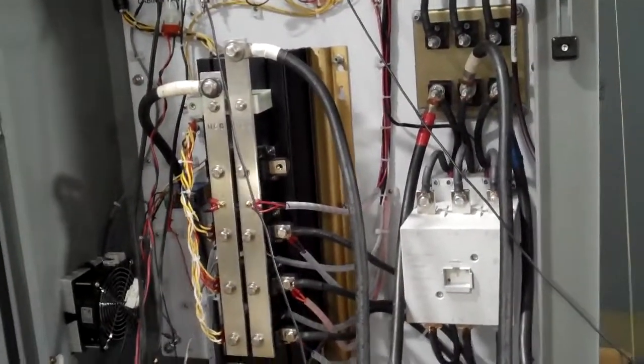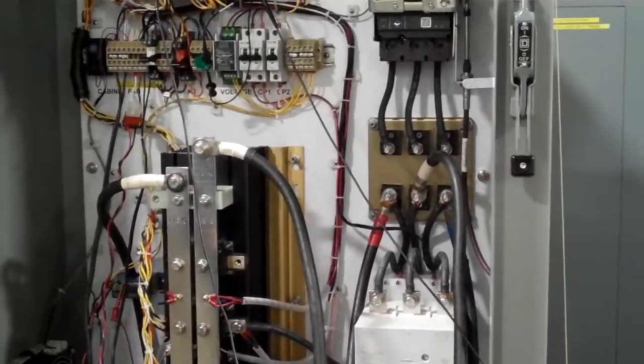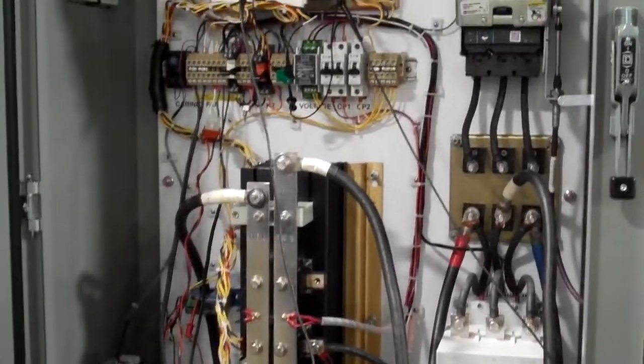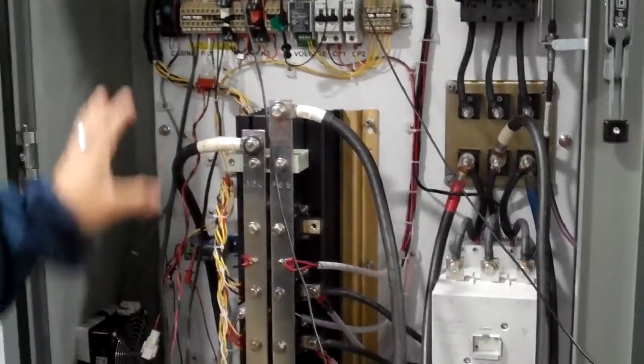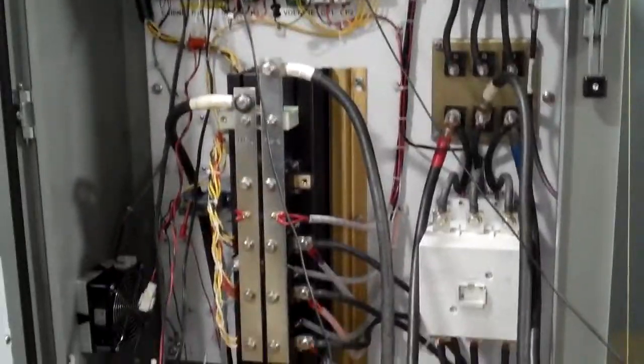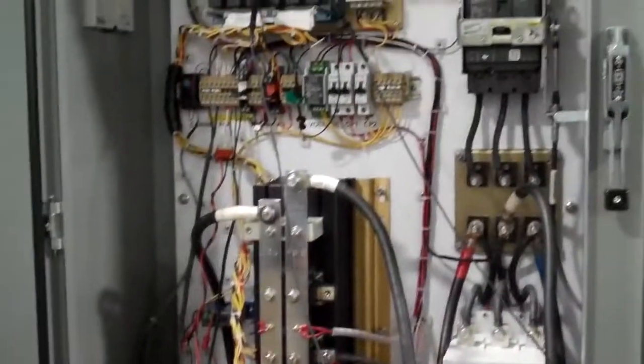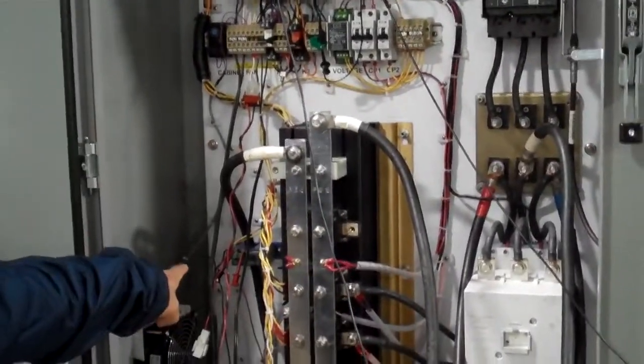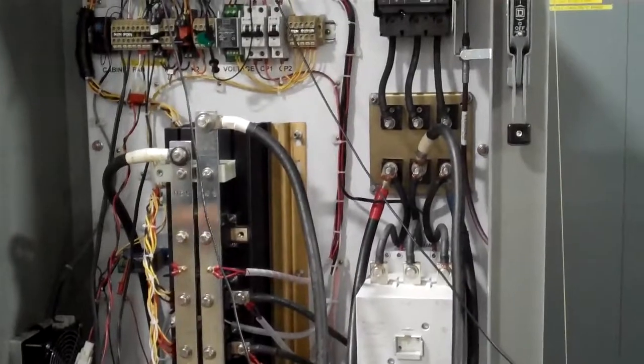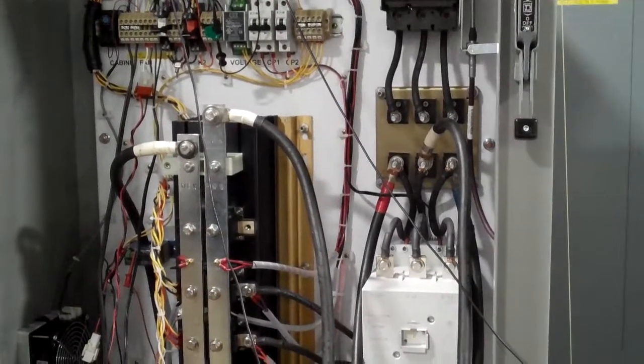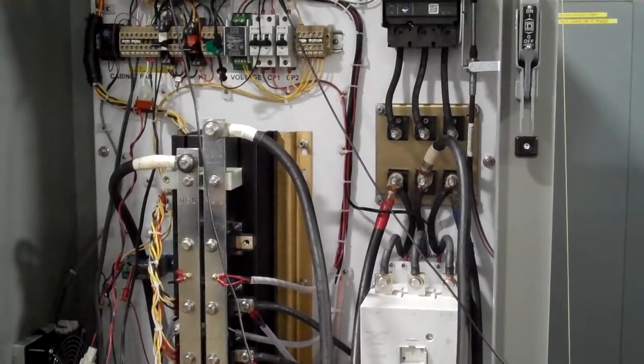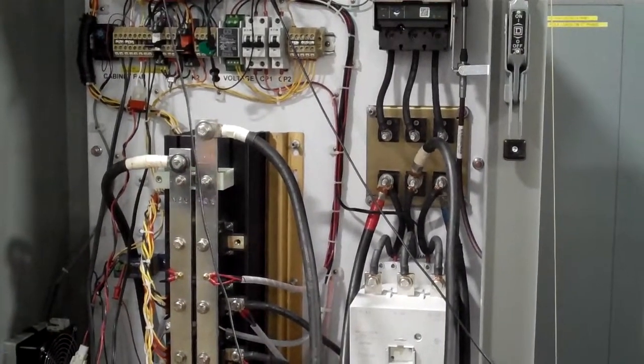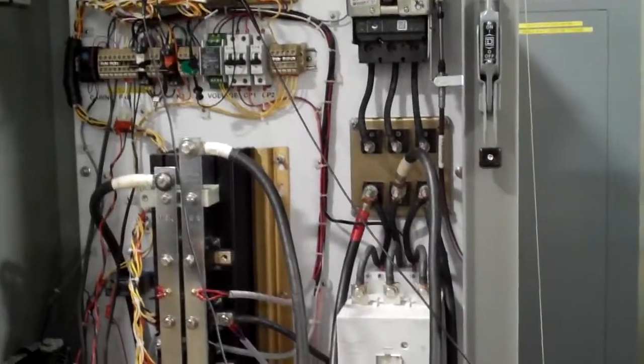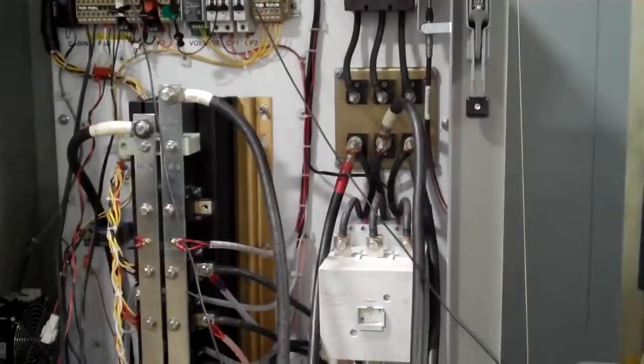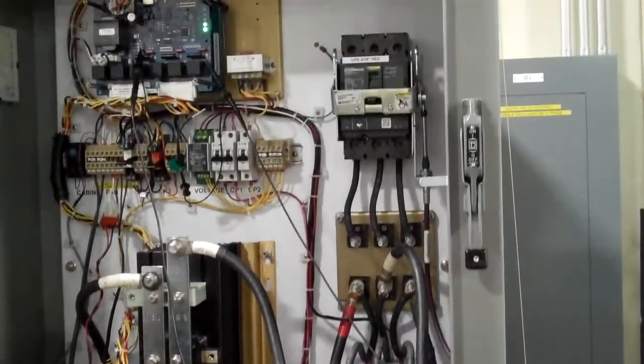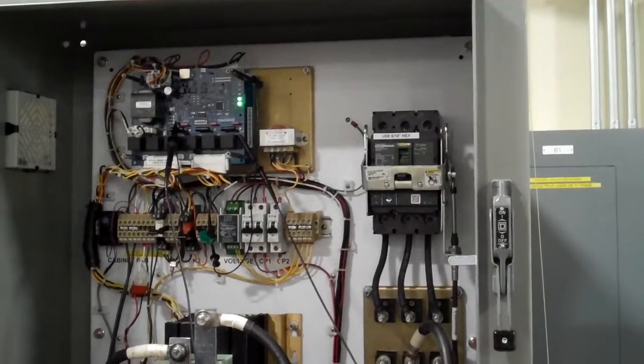What we're doing here is checking the rectifier in the cabinet for maximum output current while checking the current readback from the current transducer, checking that the fans and cooling work, and more importantly, checking that once the cabinet is closed and running at full current, we have a thermal equilibrium and that it is safe, with no overheating conditions.